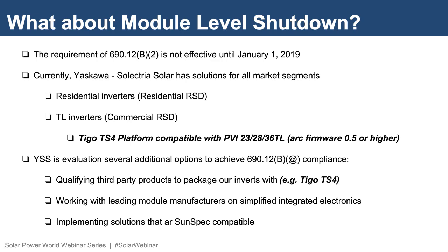combiner. But what about module level shutdown? What about disconnecting, de-energizing within that array boundary? I know it's not effective until January 1, 2019, but certainly installers and clients want that functionality today. So Solectria PVI 23, 28, and 36 TL inverters are fully compatible with the Tigo TS4 platform. Tigo is a module-level electronics manufacturer, and their TS4 platform provides that module-level shutdown, that module-level safety, which is compatible with our 3-phase transformerless string inverters.